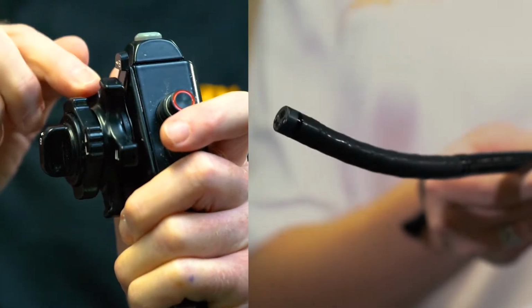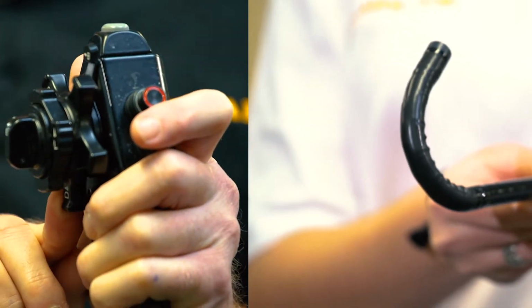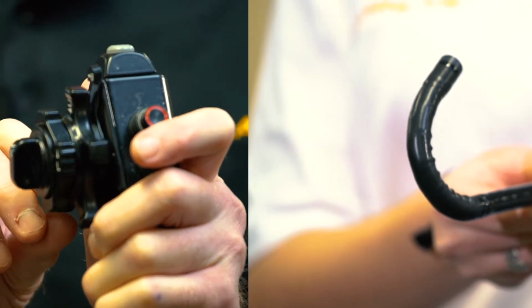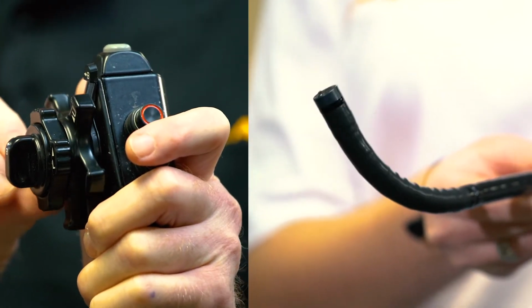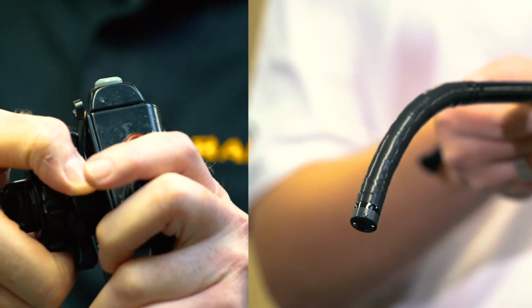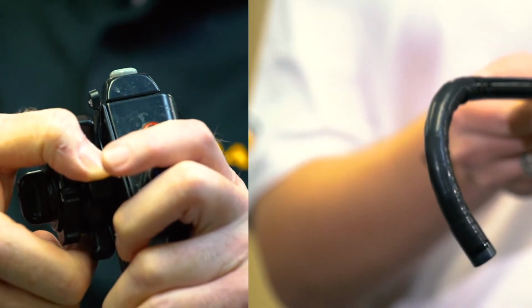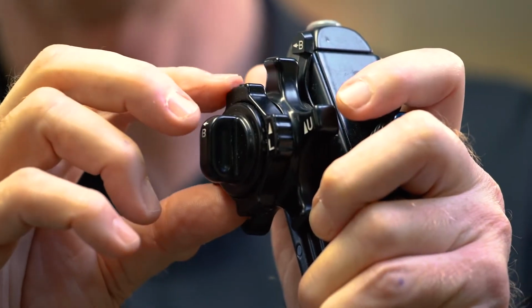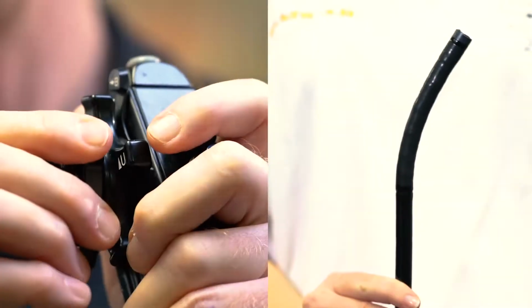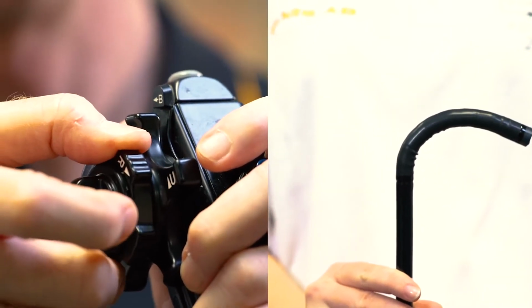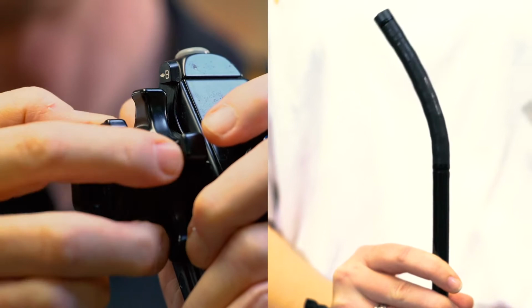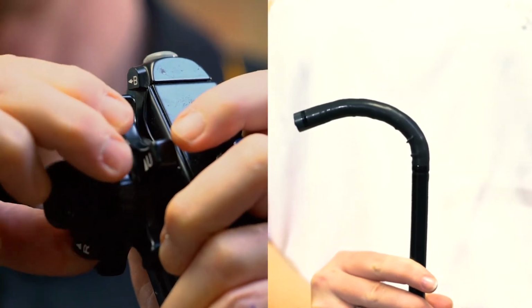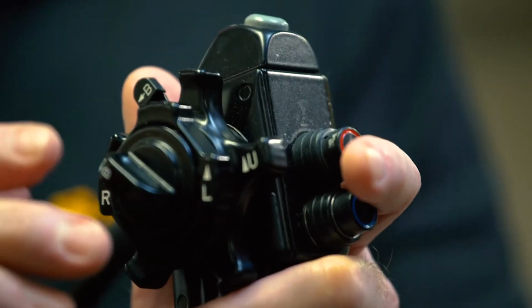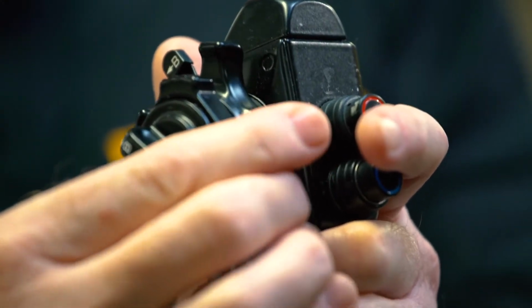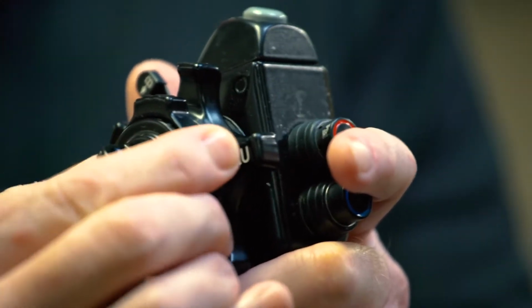Slowly rotate the larger up-down articulation knob counterclockwise to move the flexible tip of the endoscope upward. Rotate clockwise to move the tip downward. The smaller knob controls the scope's side-to-side movements. A clockwise turn moves the tip to the right, and a counterclockwise turn moves the tip to the left. Do not force the deflection control knobs. Excessive force could damage the endoscope and may cause patient injury.